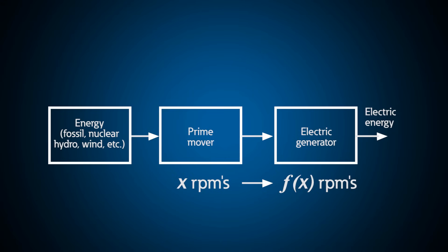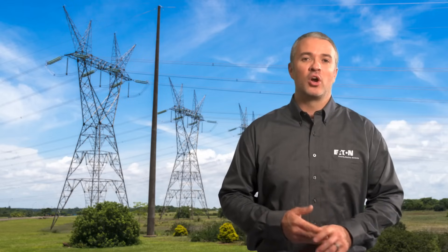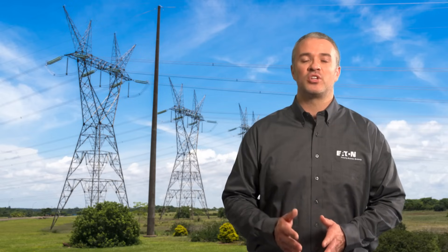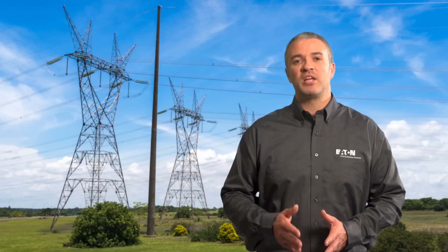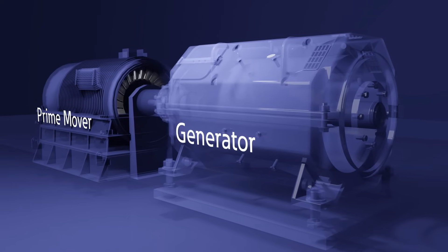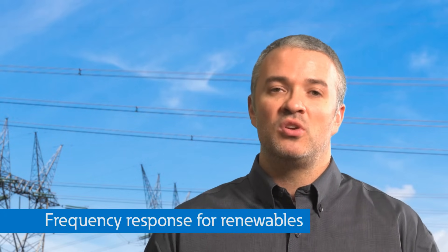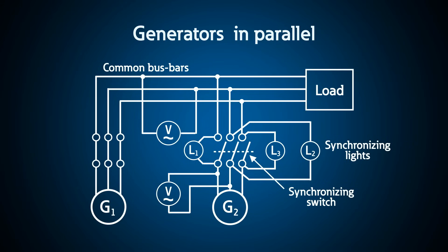Even with large fluctuations in load, large utility generators don't allow the frequency to change much because they are large rotating masses and provide significant inertia to the grid. This is extremely beneficial by stabilizing the voltage, but it could take up to a minute for these units to get frequency back to the proper level if something catastrophic happens. Some widespread blackouts have been related to significant frequency changes in large generators. Wind and solar have a much faster frequency response due to the use of electronics, but they don't provide as much grid stability as large generators with rotating inertia. For large systems, generators are paralleled with each other and must be synchronized.